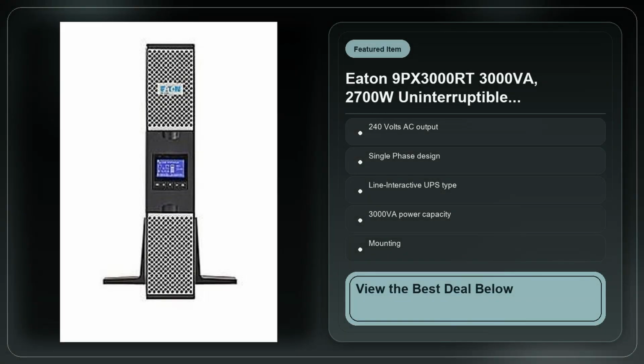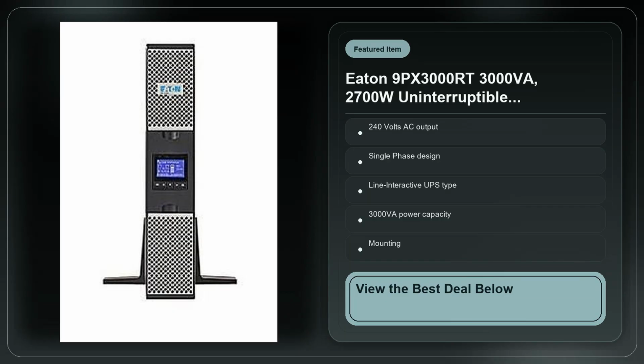Likewise, if you're looking for a UPS that can sustain a full load for an hour or more, you'll need to step up to a larger capacity or add external battery modules, which the 9PX line does support but adds cost and complexity. In those cases, the 9PX3000RT might feel like a mismatch.